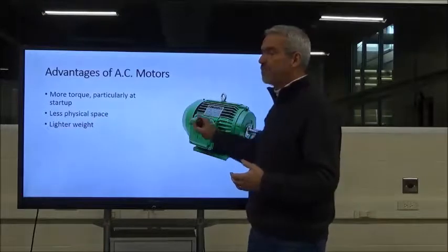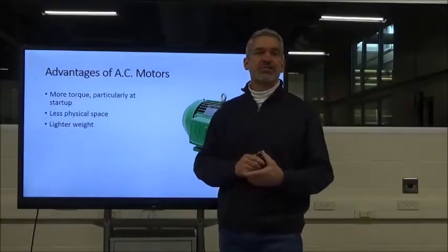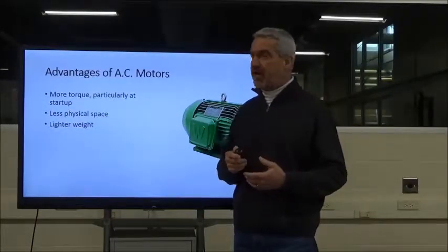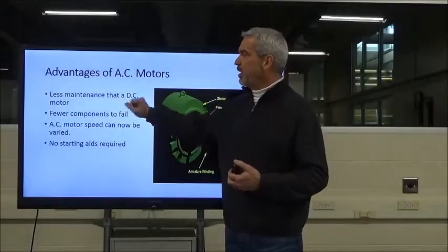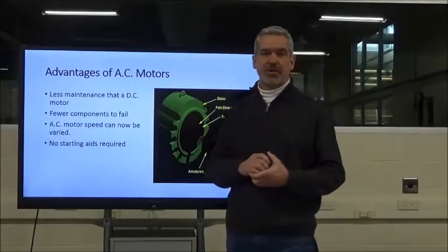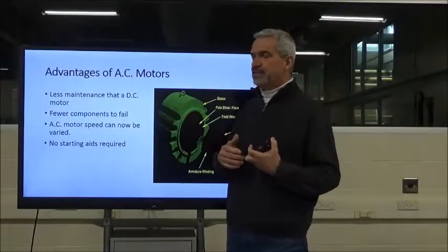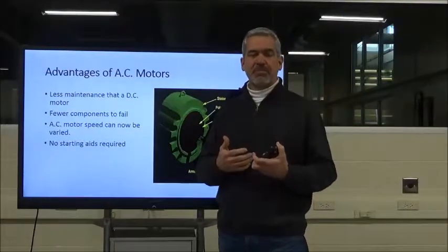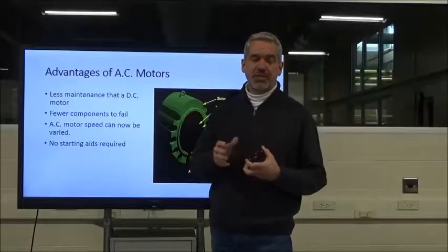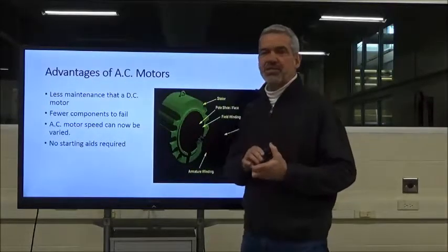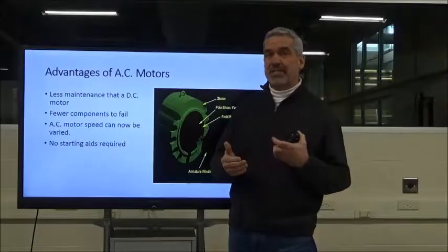A three-phase motor is smaller for the same amount of horsepower, and they are typically lighter in weight. A big advantage is that they require less maintenance than a DC motor. Previously, the only way to vary the speed of a motor was to use a DC motor — you would adjust the field voltage to adjust the RPM. You couldn't do that with AC, but that has changed.